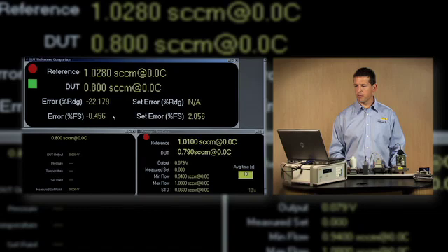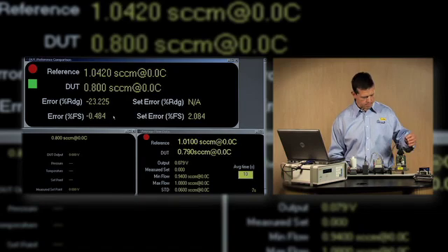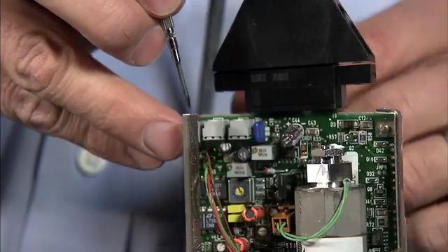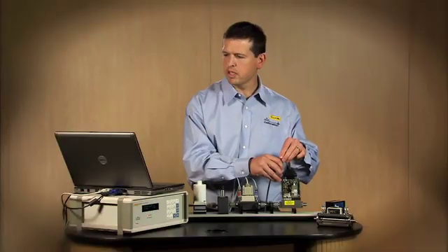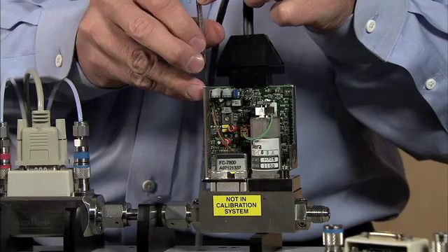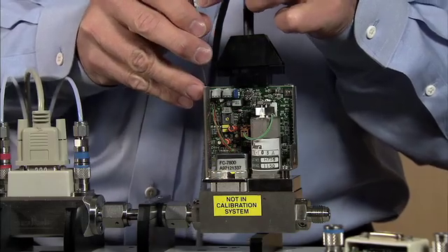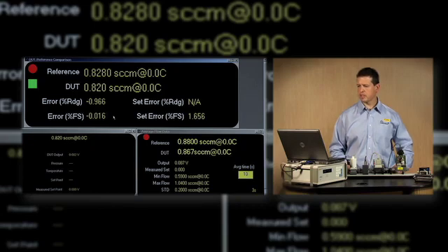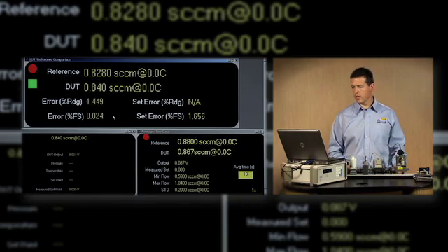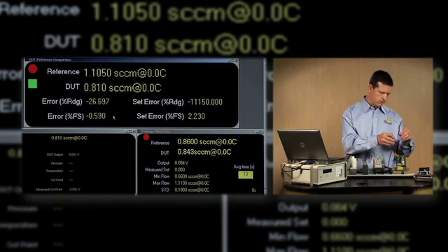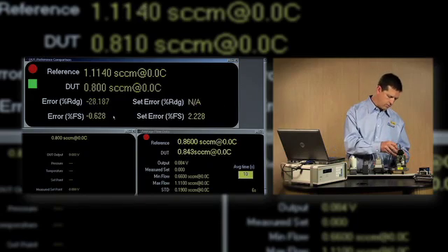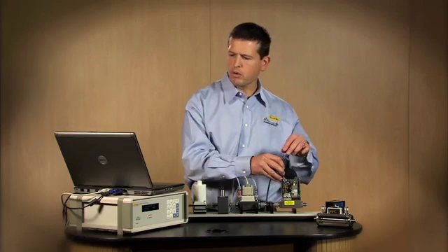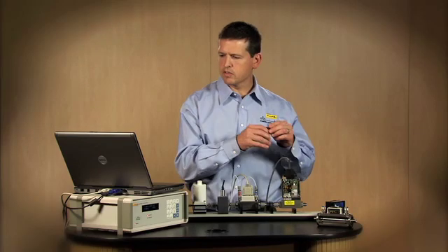So right now both of them are a little less than 1 sccm. And to adjust the MFC, I'll turn the zero potentiometer and bring its reading closer to the reference indication. So you can see now that the percent full scale error has reduced. In a lot of cases at these low flows, it will require some waiting and some patience.